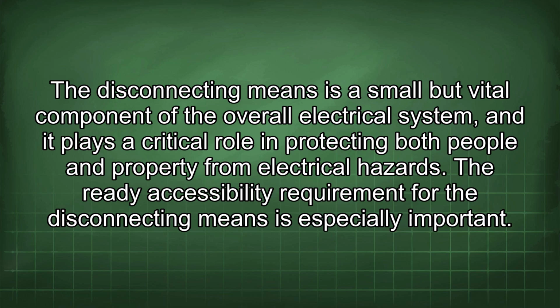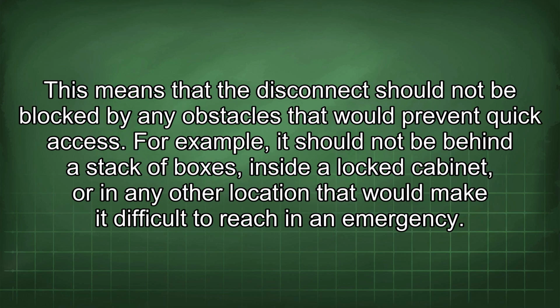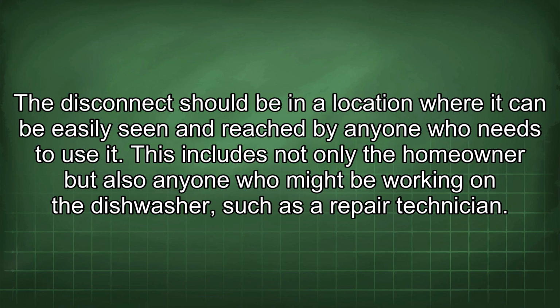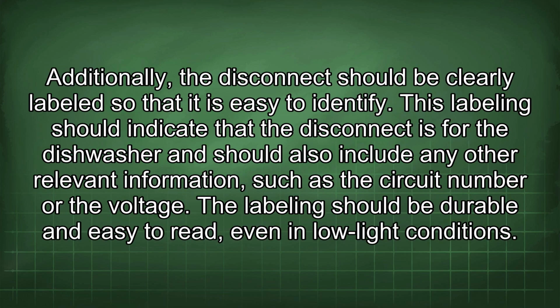The ready accessibility requirement for the disconnecting means is especially important. This means that the disconnect should not be blocked by any obstacles that would prevent quick access. For example, it should not be behind a stack of boxes, inside a locked cabinet, or in any other location that would make it difficult to reach in an emergency. The disconnect should be in a location where it can be easily seen and reached by anyone who needs to use it. This includes not only the homeowner, but also anyone who might be working on the dishwasher, such as a repair technician. Additionally, the disconnect should be clearly labeled so that it is easy to identify.